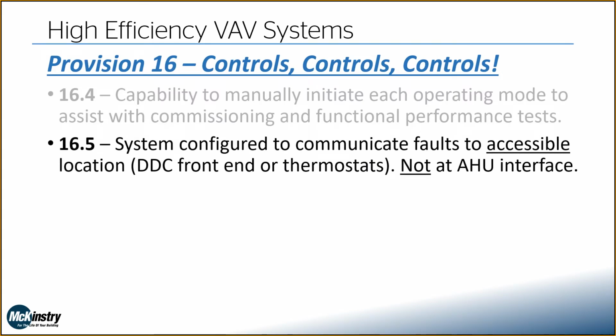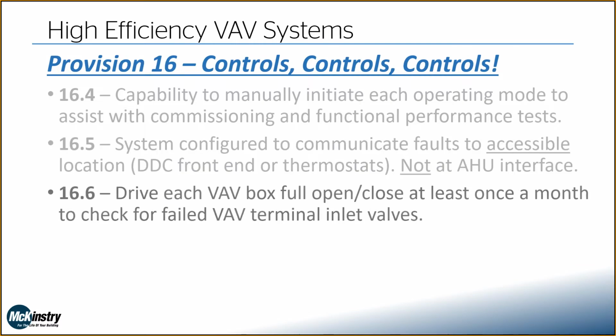The system has to be configured to communicate any faults or alarms to an accessible location. So typically that'd be the DDC front end or locally at the thermostats. Not at the air handler interface, especially if this thing is up on the roof. You shouldn't have to go up on the roof to look at your faults and alarms. It has to be reported to an accessible place. You have to have a specific sequence in place for every VAV box where once a month you drive them open, drive them closed, you check the airflow values at each position to make sure that box is working. Make sure those inlet valves are working and actually modulating the way they should.